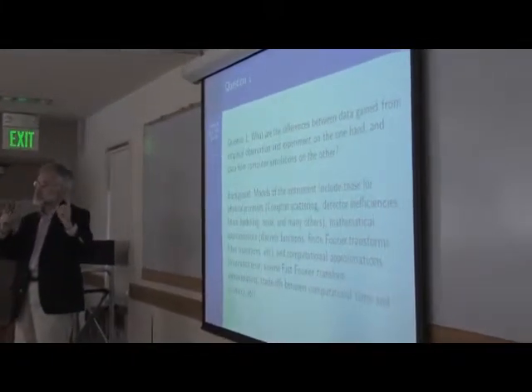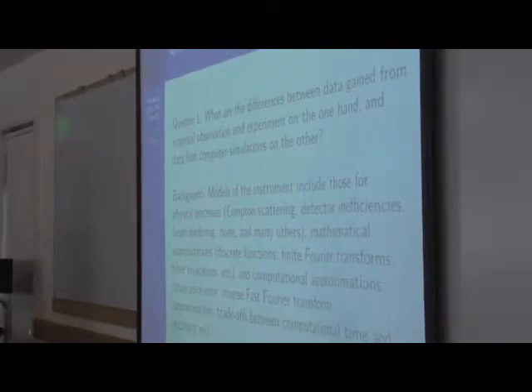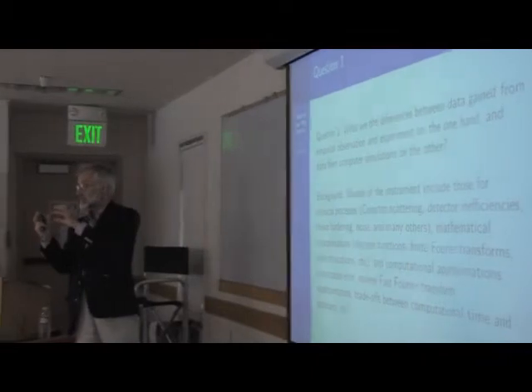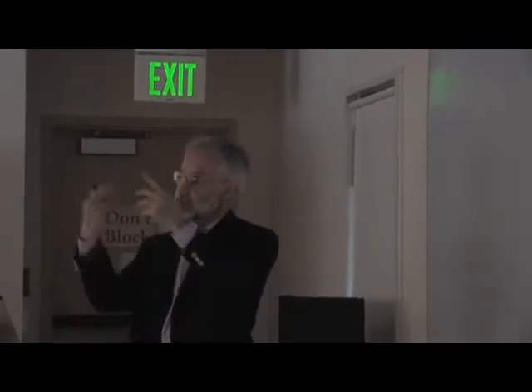You've got a combination of something that is a traditional physical instrument on which you're getting physical data, together with something that is computation. And when these things are calibrated, they calibrate using a lot of phantoms — you can have physical phantoms and simulated phantoms. So instead of putting in physical data coming out of the experiment, you substitute simulated data, and the constructed image that you get, if the instrument and algorithms are working correctly, will be almost indistinguishable from the image you would get from a real object.